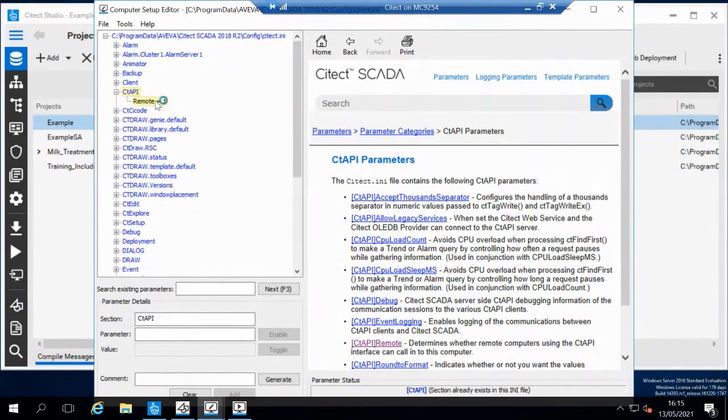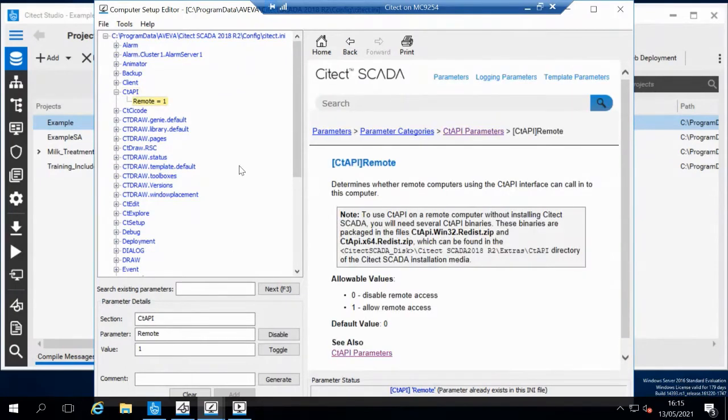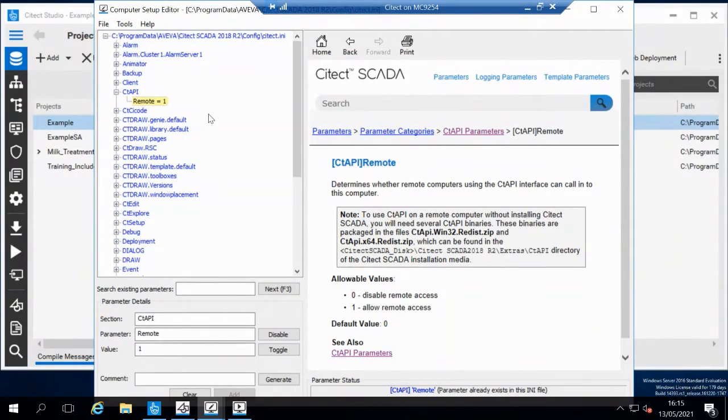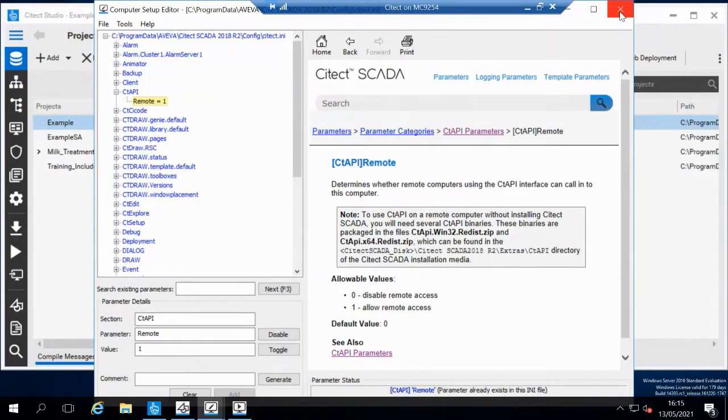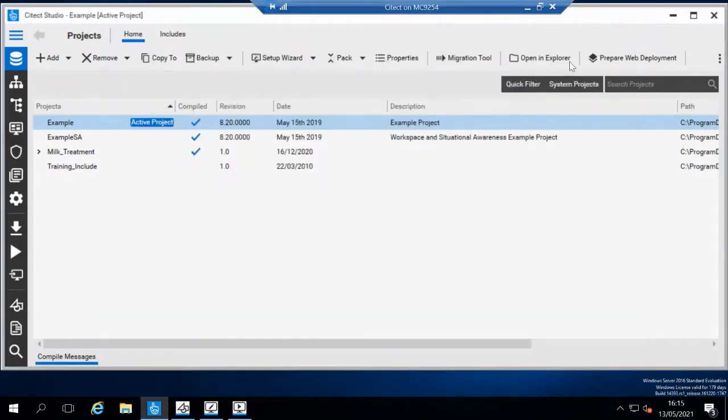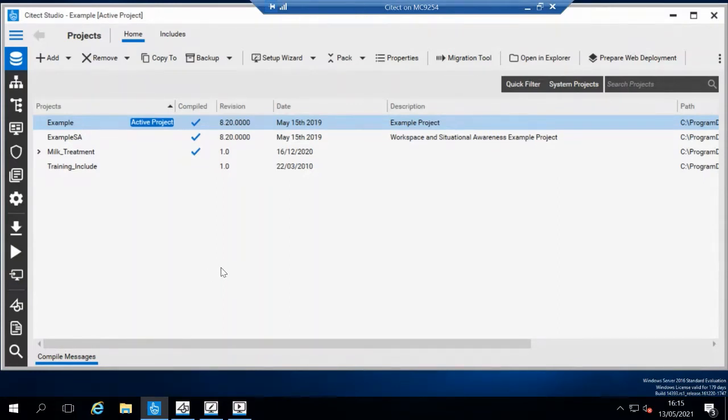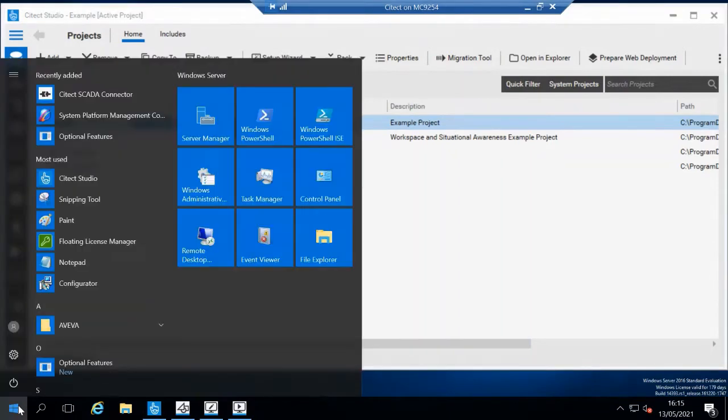You need to set CtAPI Remote equal to one, and that will enable exporting the data into Insight. Additionally, you'll need to download the Citect SCADA connector, which is a free download from within Insight, and put that onto your Citect node.